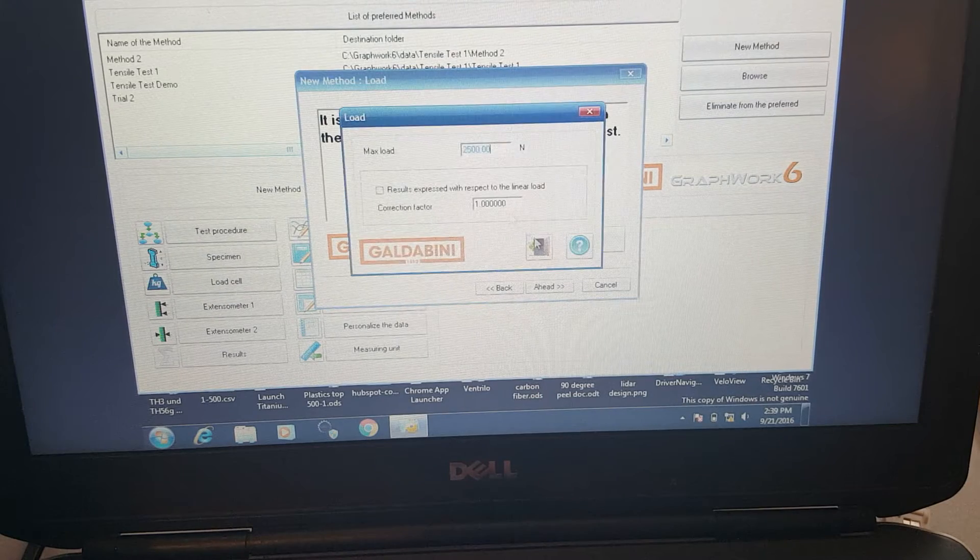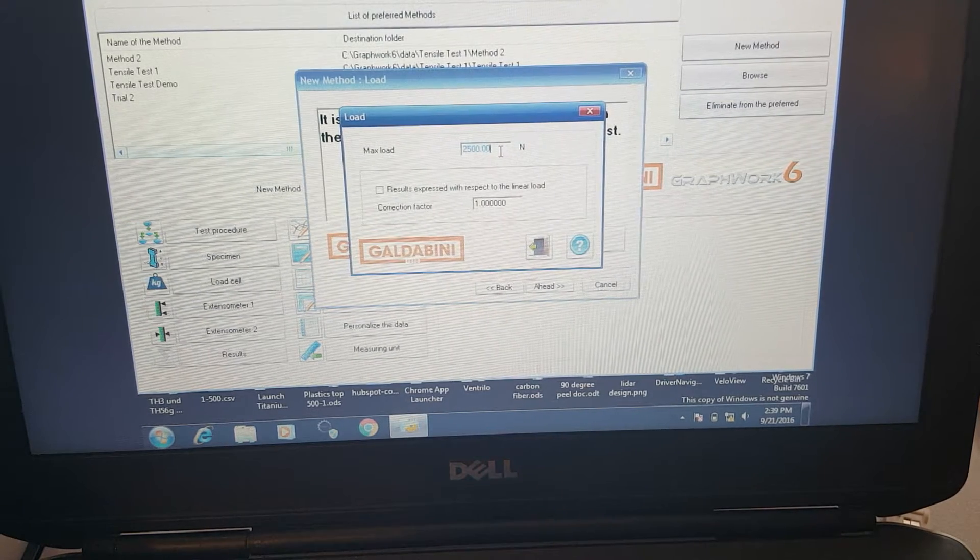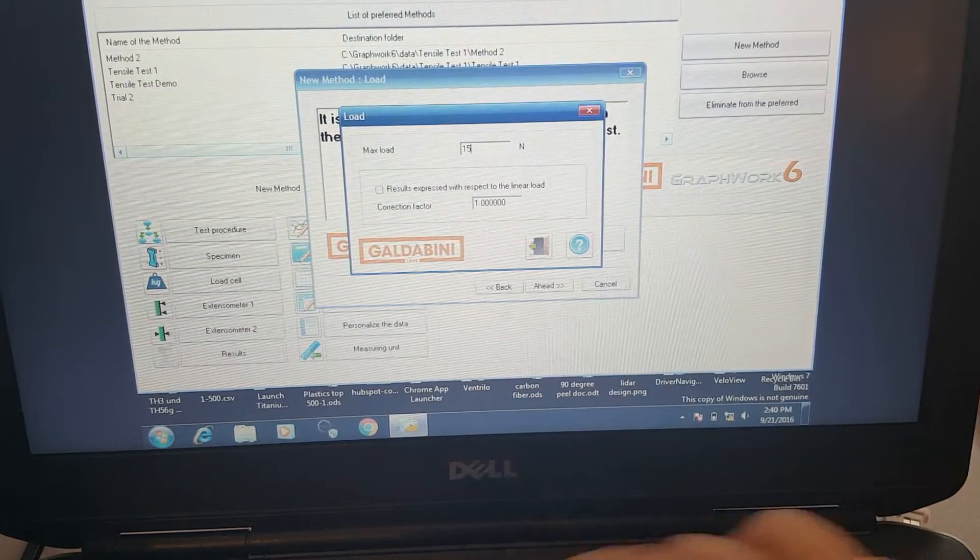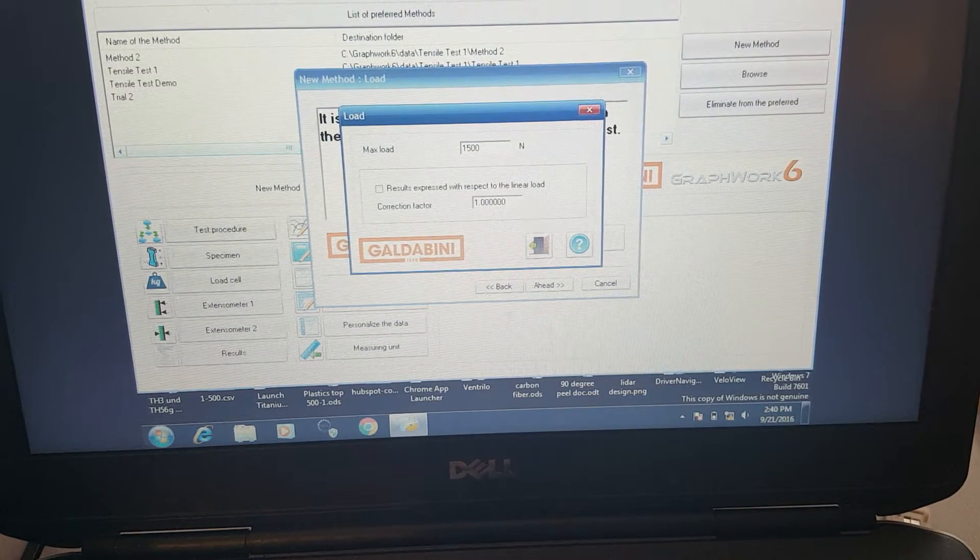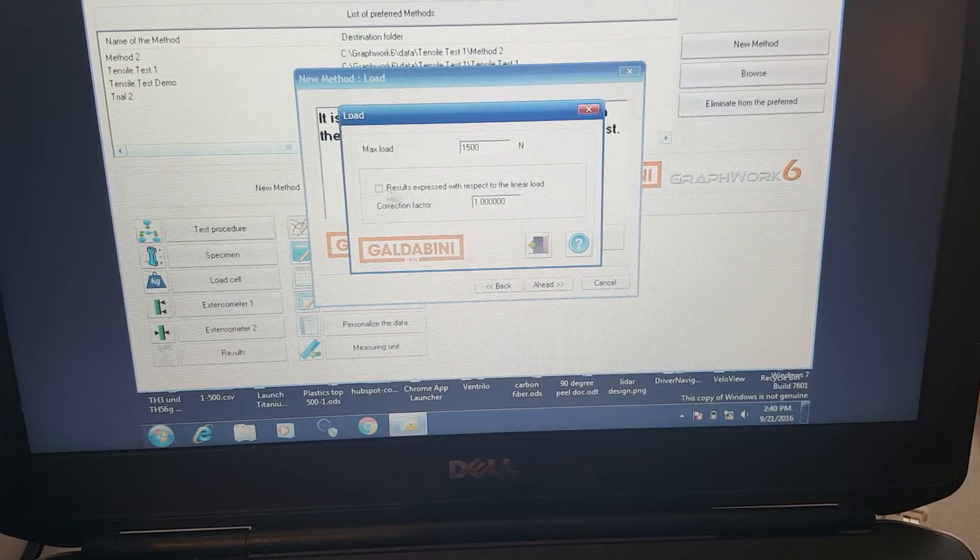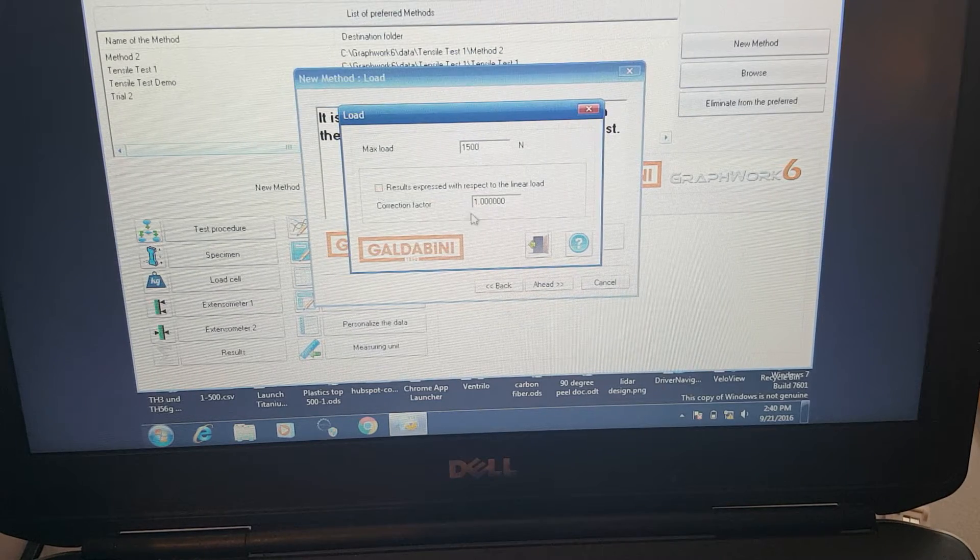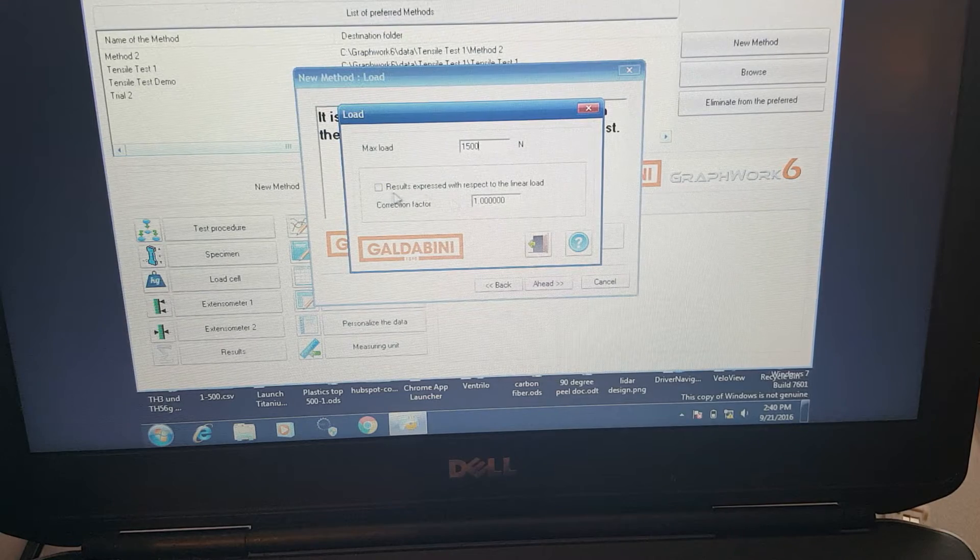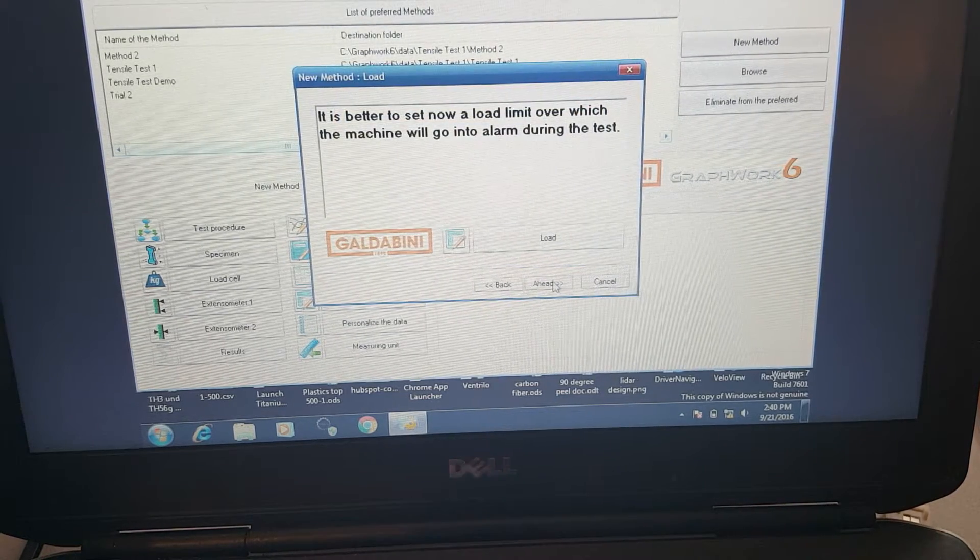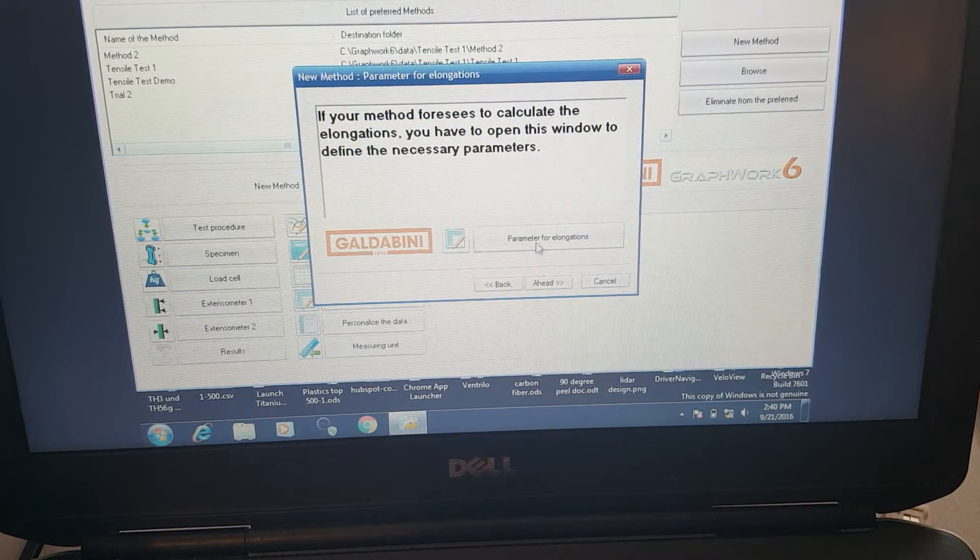Here we can set a load limit on the machine. This is nice because it can protect your load cell if you might be testing over the limit. So we'll go with 1500 newtons, about 60% of our max possible load with this load cell and machine.